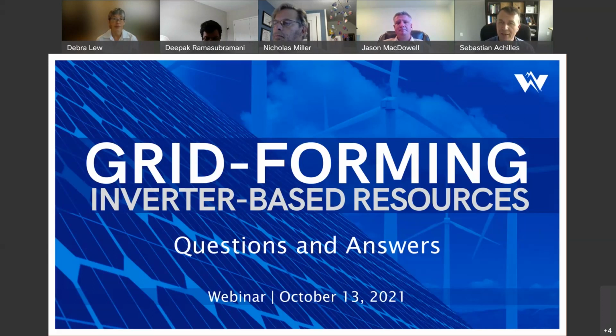Regarding the angles going apart, in a way that happens because we keep pushing power when the system cannot take it. So during a fault, if you push too much power, like Nick was describing in his presentation, the angles tend to grow apart. But it's common practice now for inverter-based resources, grid following or grid forming, to identify conditions in which the system cannot take too much power and reduce the amount of active power.